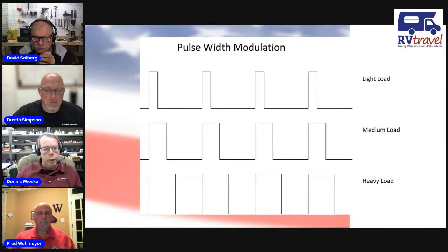Gradually the chargers came along, and these are all old style chargers, so big transformers, a lot of weight, and not very efficient, usually about 50%. With the newer chargers, you had two options: one was 12 volt to run the RV, usually rated maybe 30 to 50 amps for lights, fans, and other electronics, and usually 8 to 15 amps of battery charging, with the option of running strictly off the battery or charging it.